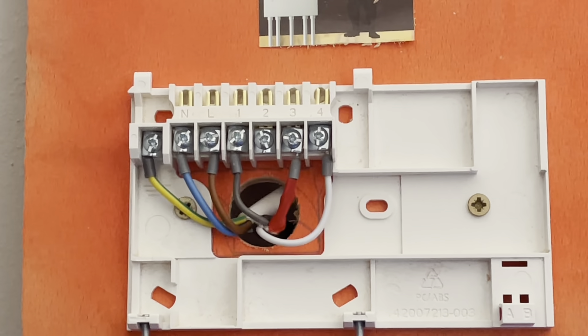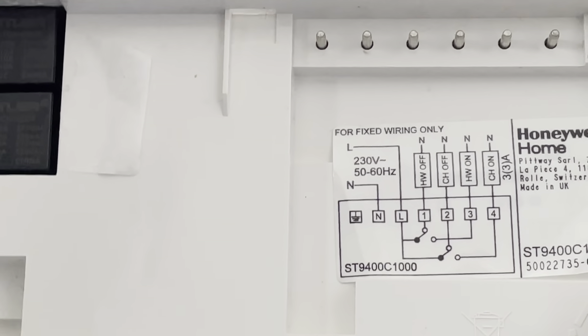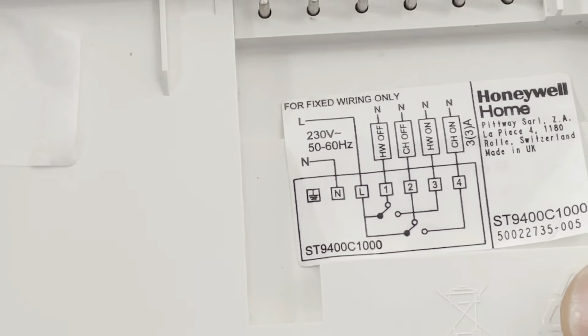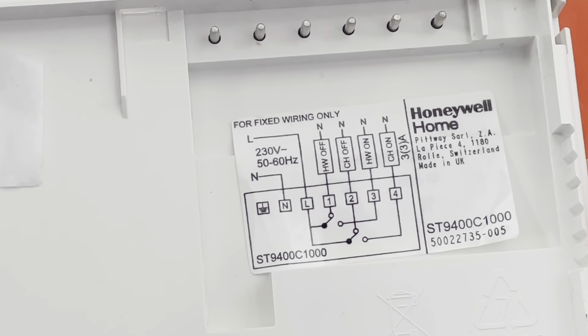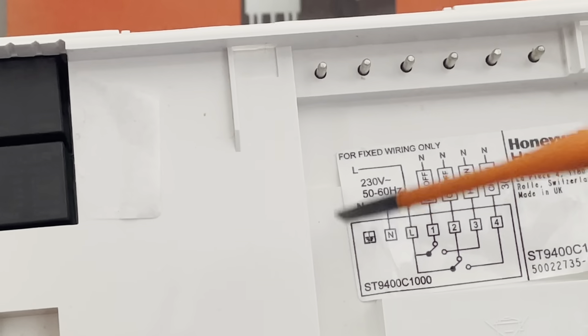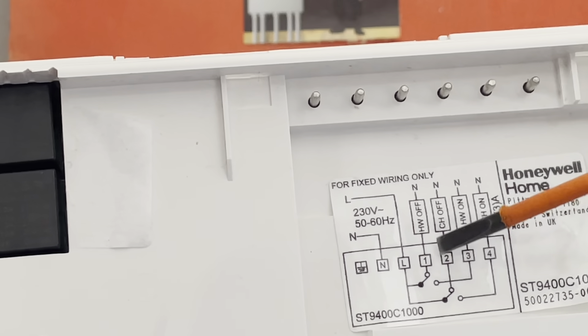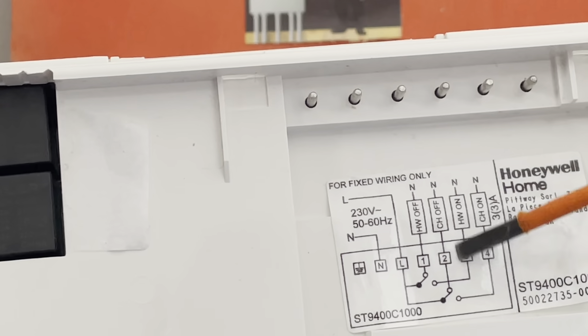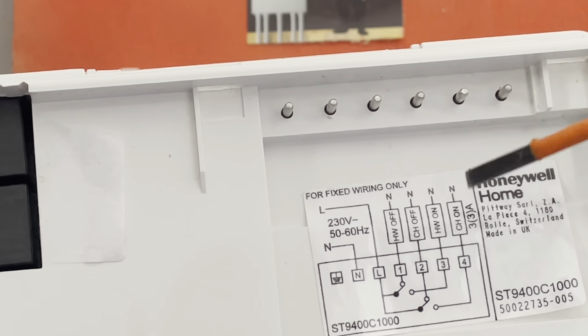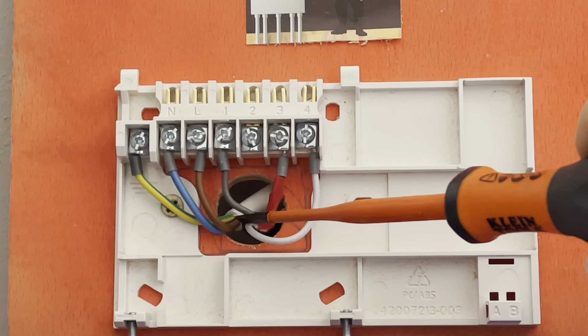With the programmer, I said I was going to go into this in depth, just so you don't get confused. On the back of the programmer there'll be a little wiring diagram — every programmer you have may be slightly different if it's a different model. On here you can see your live, neutral, and earth coming in. Then you've got hot water off — which is important in a Y plan system — and then central heating off, which we never use, and then hot water on and central heating on.